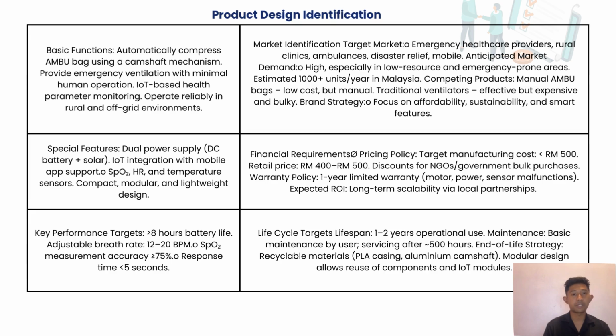Positioning the Smart Camshaft Ventilator as a smart, sustainable alternative, the target manufacturing cost is below 500 ringgit, with a selling price between 400 to 500 ringgit, and a special rate for NGOs and government agencies. It delivers up to 8 hours of battery life, respiratory rates of 12 to 20 BPM, and rapid response under 5 seconds. Designed for 1 to 2 years of use with recyclable material and modular components. It meets ISO 80601, IEC 60601, and RoHS safety standards.